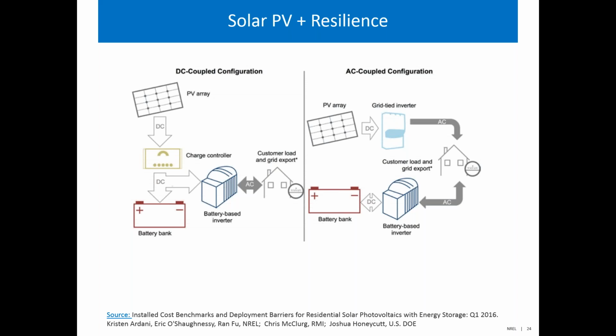When wired for backup power, it is common to install a critical load subpanel and use PV plus energy storage systems, like a battery bank shown on the screen, to provide power to essential loads. These critical or essential loads could include refrigeration, essential lighting, pumps, and specialized equipment in hospitals, just to name a few examples. If configured correctly, this system can provide power to those systems during a grid outage.